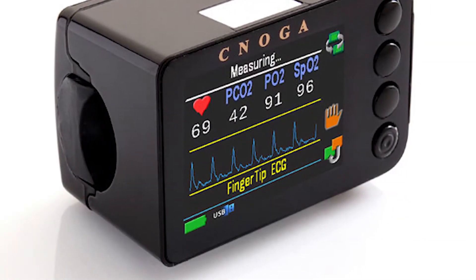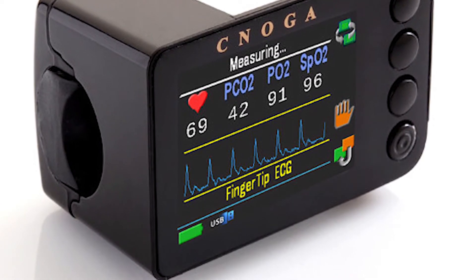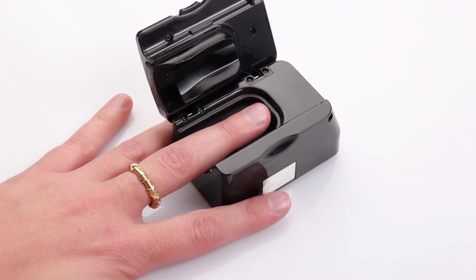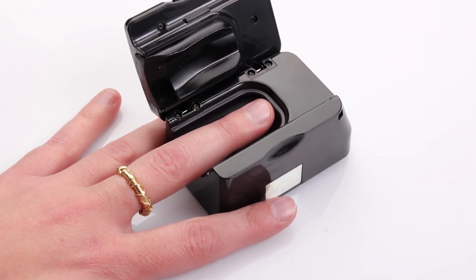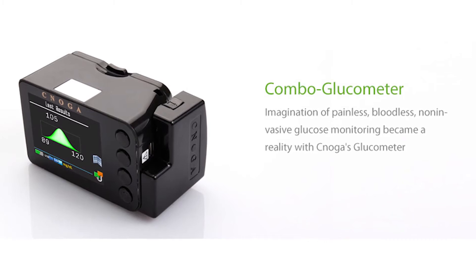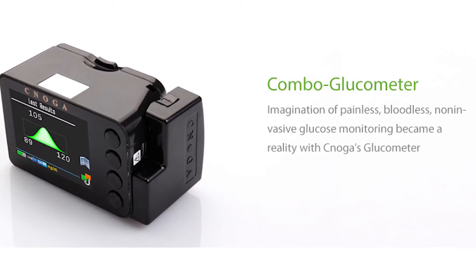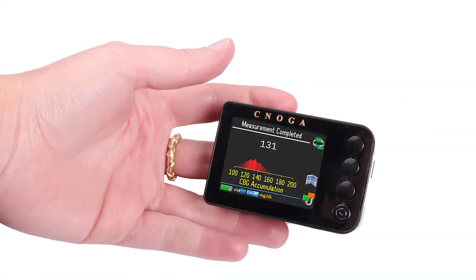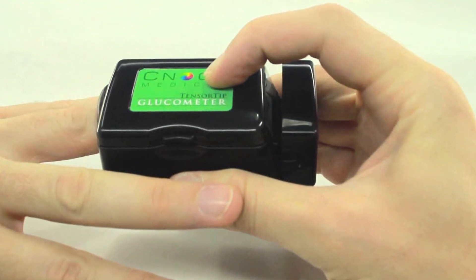What is the mechanism of action? Four LED lights shine wavelengths from visible light to infrared through the fingertip. As the light wave passes through, some of it is absorbed and the light signal is changed. A camera sensor detects the changed light signal in real time. The device uses patented algorithms and a vast amount of data. Cnoga analyses the correlation between the signal and the bioparameters.